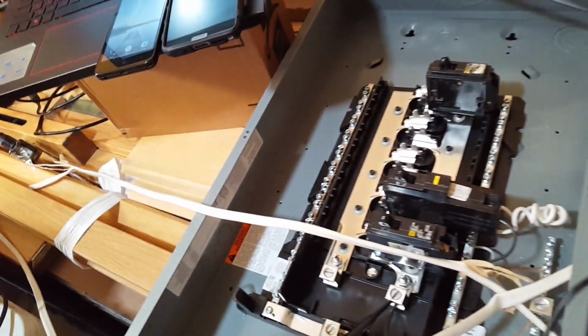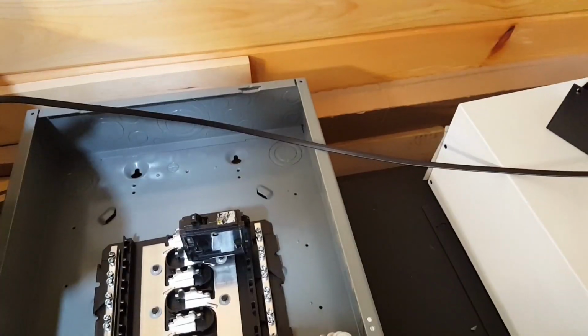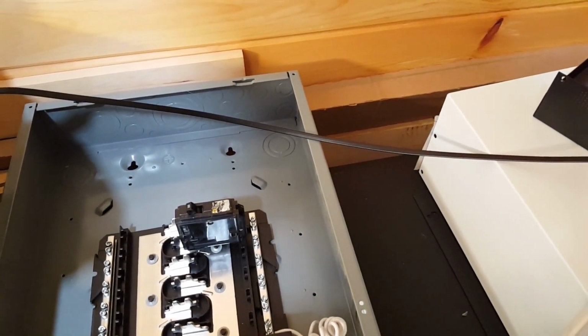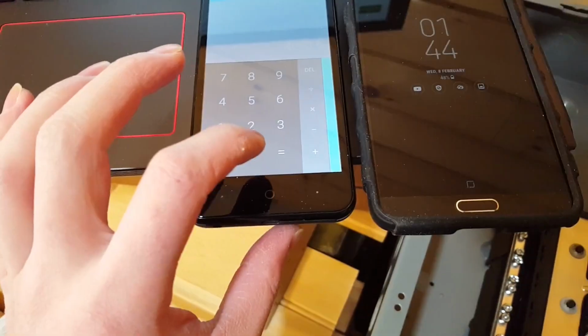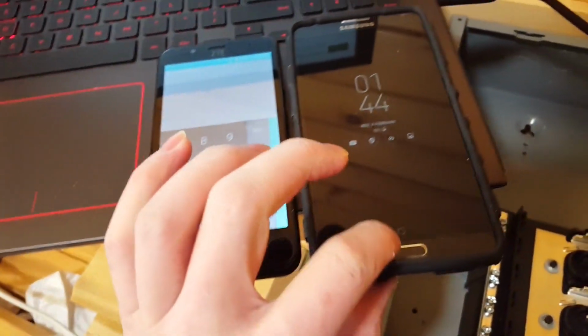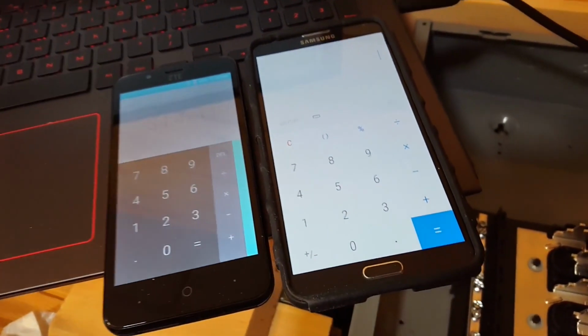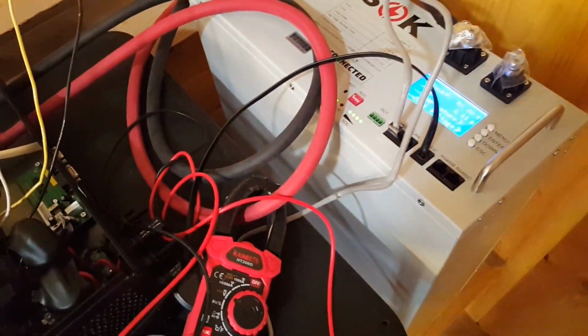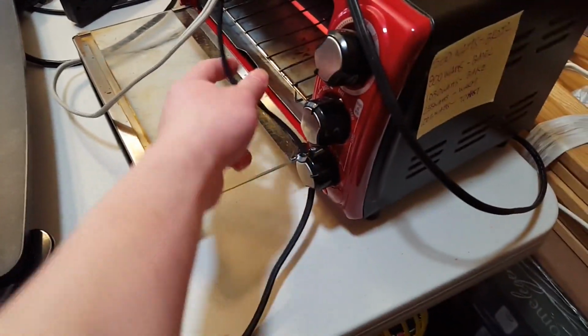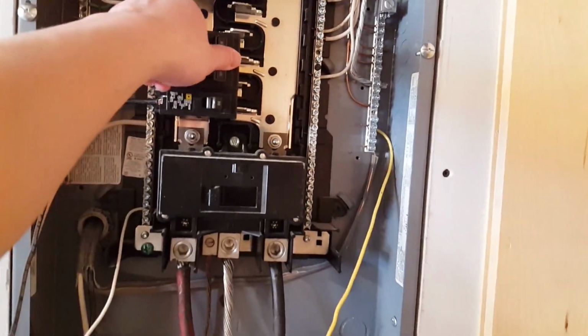So it's 34.4 amps times 119 volts. That gives us 4,093 watts on the AC load. We will average the DC amps on the DC side. So the loads are back on. This is on, that's on, and this is on at 1,000. Going to battery mode.